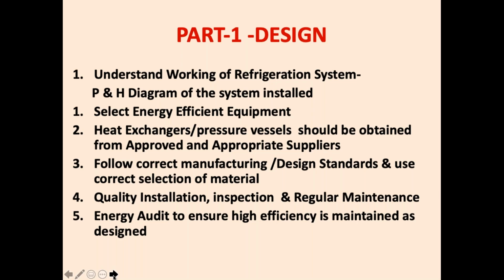Select energy efficient equipment. Heat exchangers and pressure vessels should always be obtained from approved and appropriate suppliers. A very, very important point. This is the mistake 90% of plant owners make. They take a drawing from a designer and get the heat exchangers or pressure vessels fabricated at site or at some second grade workshop which does not have the ability to do pressure vessel fabrication. So fabrication of pressure vessels and heat exchangers is very, very important and should be done with appropriate and approved suppliers.